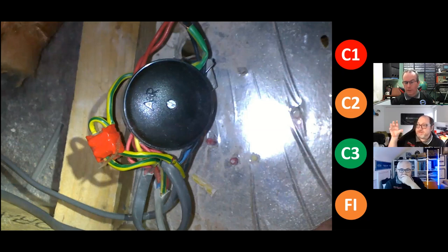So I need to use the coding as best to explain. Well, that's why you have those lovely codes with the observations. You can just put the codes that you need to with the observations. When you see something like this in a loft space, the first thing you're going to want to do is obviously assess the risk here. But then you're going to want to look further at the connections to the luminaires themselves to see if there's another connector, a taped connector box floating or another joint or something.